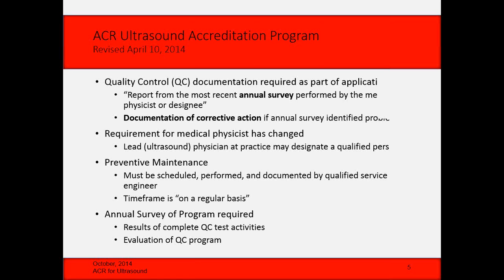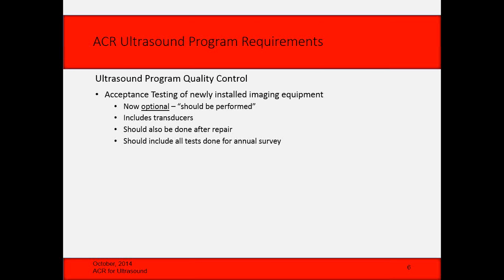There is quality control now required as part of the ACR ultrasound programs. So I'm going to go through the different types of quality control and whether it's required, optional, and what the ACR says about that. Acceptance testing used to be required. It is now optional, and the ACR says it should be performed, which I would agree with, by the way. And that should include, or it does include, transducers. It should be done after a repair to make sure that the equipment is working properly after the repair. And the acceptance testing, if it's done, should include all tests done for the annual survey.